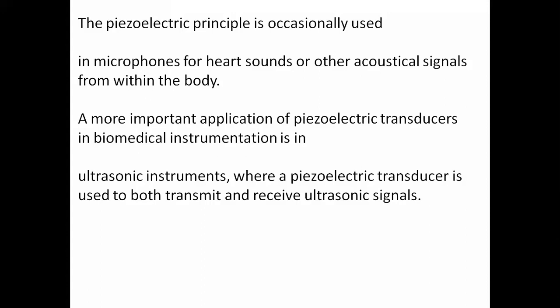In the stethoscope we have a microphone, and that microphone is based upon the principle of the piezoelectric effect. By putting it on the chest of the human body, the variations or displacement or pressure applied on this piezoelectric material will be converted into corresponding electrical signals, and those electrical signals will be noted.